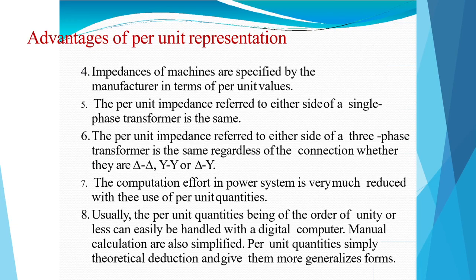The next advantage is that impedances of machines will be specified by the manufacturer in terms of per unit values. Fifth, the per unit impedance referred to either side of a single phase transformer is the same. Per unit impedance referred to either side of a three phase transformer will be the same regardless of the connection, whether it is star-star, star-delta, delta-star, delta-delta.